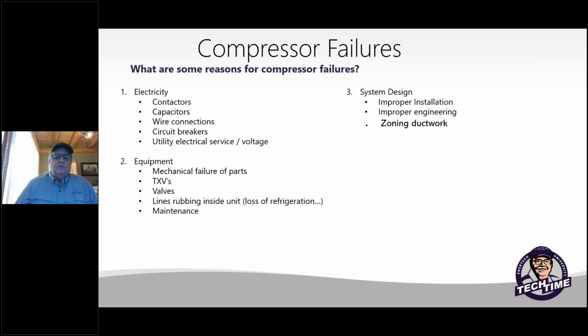Wire connections, bad connections, loose connections tend to heat up, turn wires darker colors, and also reduce the voltage on one of the legs going into the compressor. So they're very important. Circuit breakers are really important to find out as well. I've seen bad loose connections, burnt connections in the breaker panel at a circuit breaker, creating poor voltage to the unit as well. Not always visible when you check it when it's not running, the voltage is there, but trust me, you could have problems. So checking the electrical panel at the circuit breaker is also a very good thing to remember.